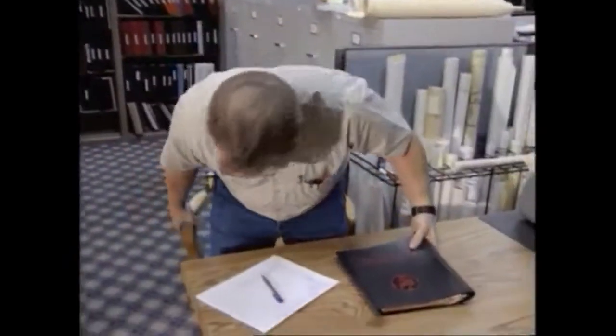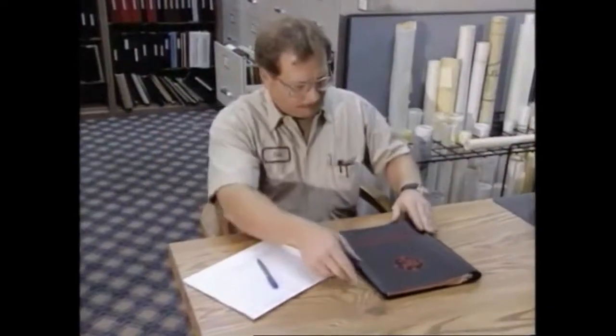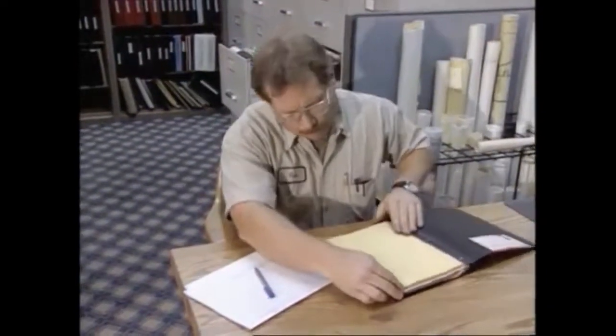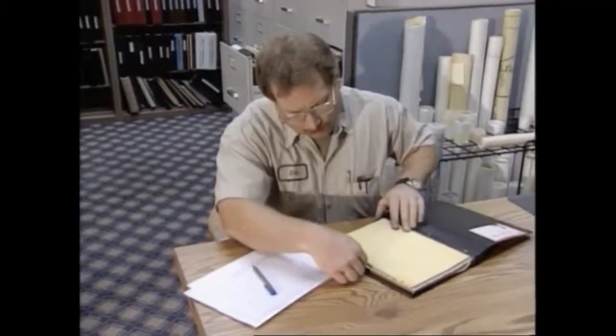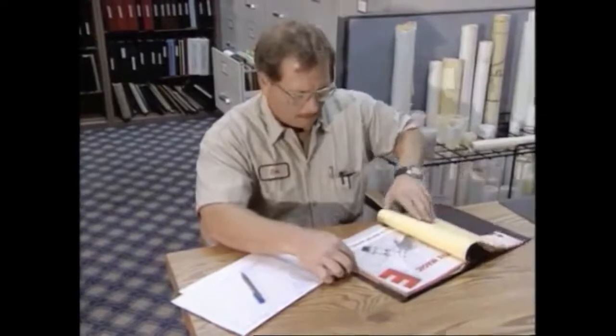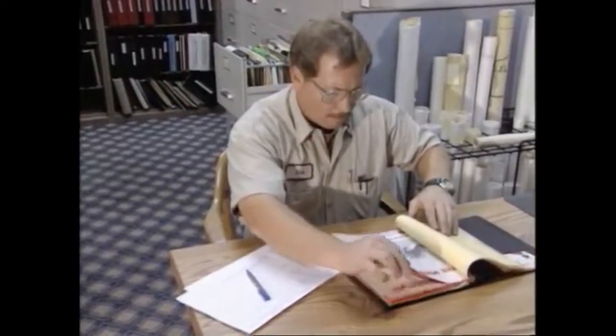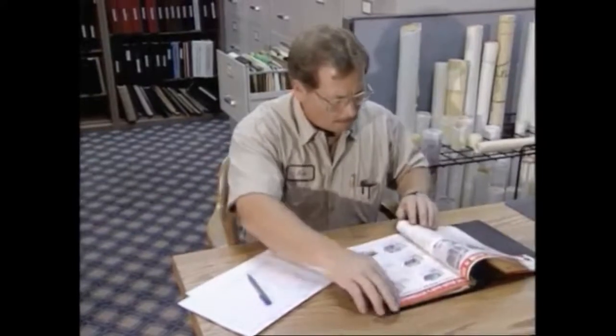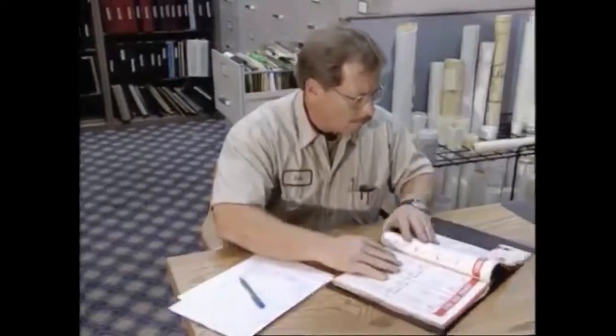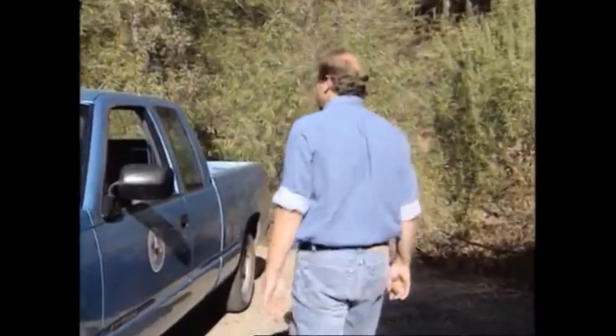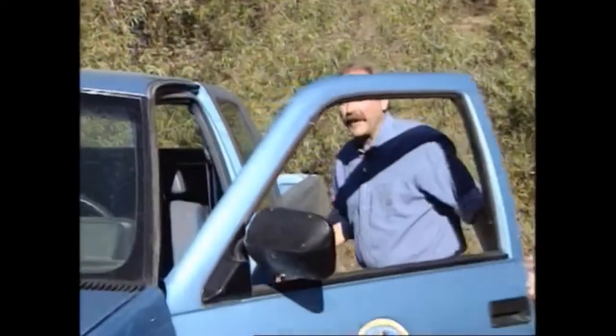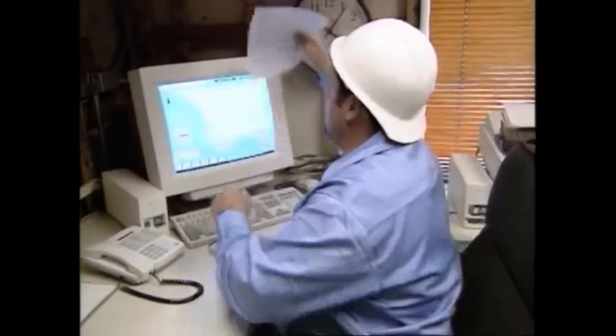The first thing to do is make a list of everything that needs lubrication, down to the smallest item, including chains, rollers, and sprockets. After you have listed every item on paper, go through the manufacturer's instruction books to determine the frequency and type of lubrication required. Next, determine the amount of each lubricant required. Determine the location of fill plugs, drain plugs, oil levels, sight glasses, dipsticks, grease fittings, and other important items. Once you've gathered the information, enter it into your equipment history cards or enter the data into the computer.